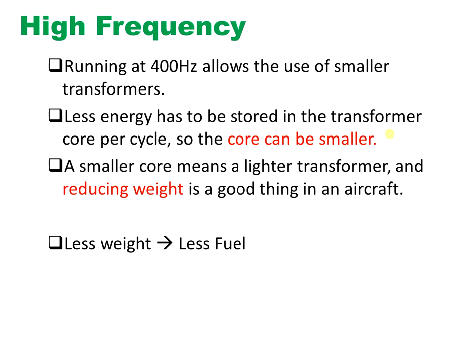The main reason for using 400 Hz is that it requires smaller transformers — the core size is smaller. Every cycle, the transformer core flux per cycle is less. The advantage is a smaller transformer core, which leads to less weight. Less weight in a flight means less fuel is wasted. That's the reason: the high frequency of 400 Hz ensures transformer core sizes become smaller, which ultimately leads to lesser fuel consumption.